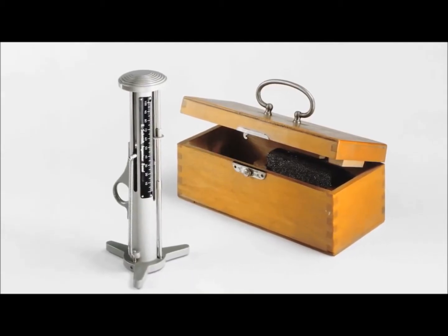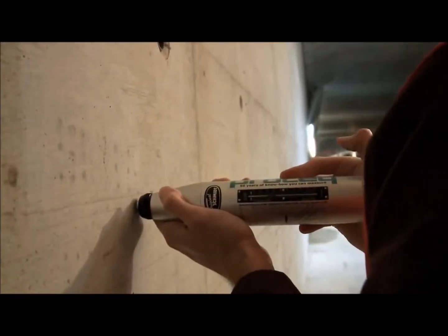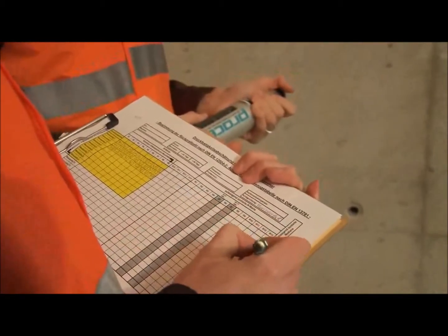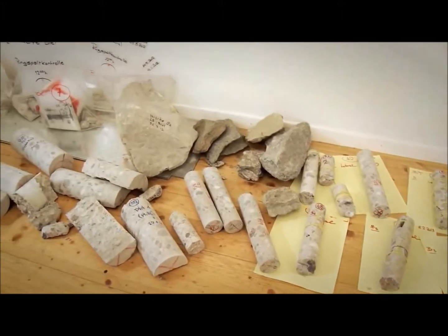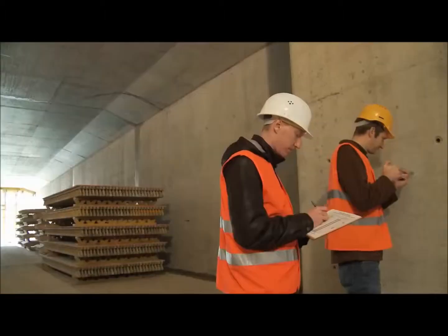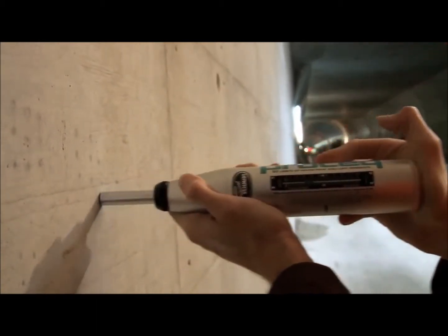The concrete test hammer invented by Ernst Schmidt and introduced by Proceq at the beginning of the 1950s remains to this day the most widely used non-destructive test instrument for a rapid assessment of the condition of a concrete structure. One of the most important parameters required by engineers is the compressive strength of the concrete. The permission to take cores from existing structures is often severely restricted or even forbidden. In such situations, the rebound hammer is the only viable alternative to estimate the compressive strength of the concrete.